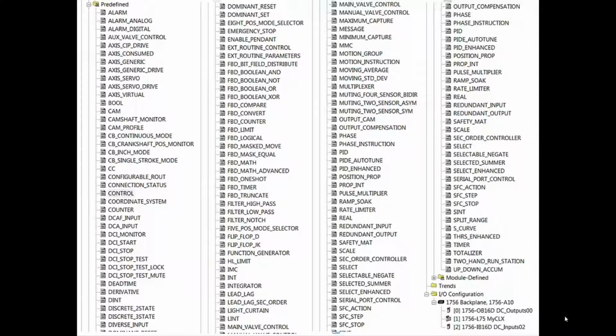Although you can create an instance of these data types, you would not ordinarily do so separate from defining a tag name in association with an instruction that will then execute with that same data structure. So ordinarily you don't go in and create a tag and use these data types here. Now the atomics you do, but the others typically you will create an instruction and then put a tag name in associated with that instruction and define it. It will be defined. For instance, like a timer.